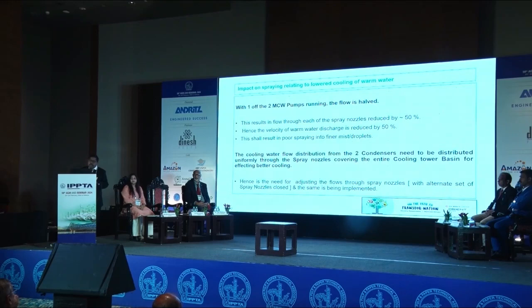With one of the two MCW pumps running, the flow is halved. This results in flow through each of the spray nozzles reduced by 50%. Hence the velocity of warm water discharge is reduced by 50%. This shall result in poor spraying, with thinner mist droplets.